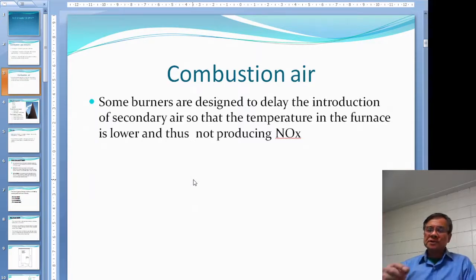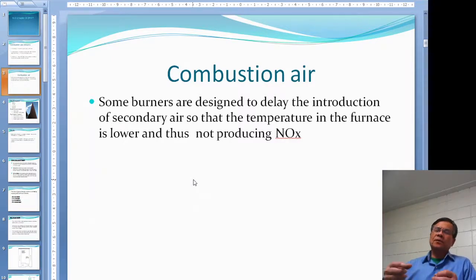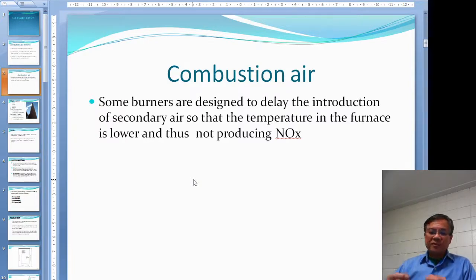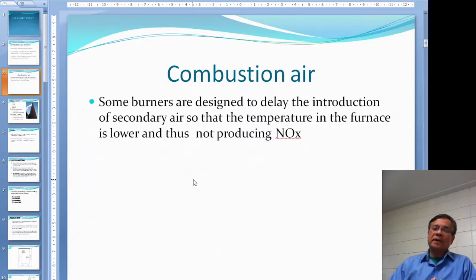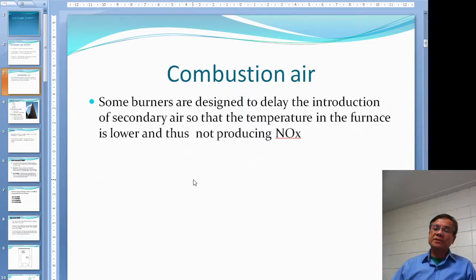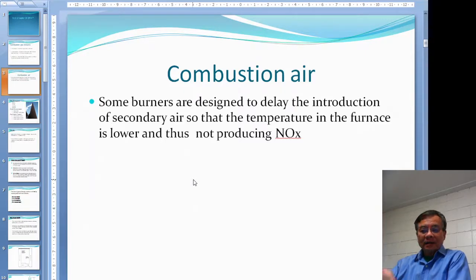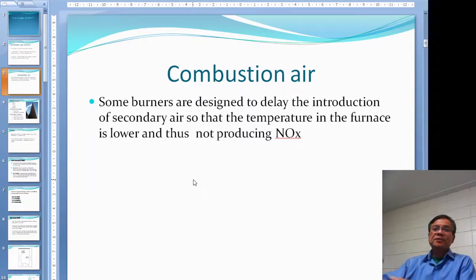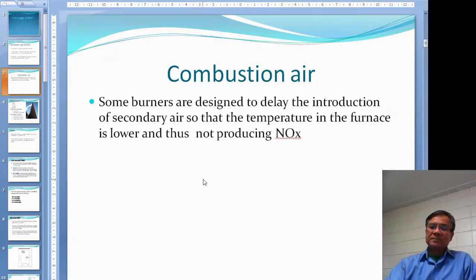If you burn all the fuel at once, the temperature would be really high and will produce NOx. In order to avoid acid rain, which comes from NOx, you want to burn a little bit of fuel first, then introduce some secondary air, and burn in another stage. Sometimes you may have a three-stage furnace so that not all the fuel burns at once, resulting in a lower temperature inside the furnace.